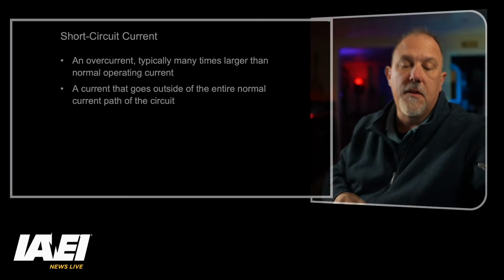So if you think about a circuit, and you have a circuit breaker back in your panel board, you have current coming out that hot wire, the black wire, like in a residential dwelling unit, from an NM wire perspective. It comes out that black wire and it comes back the white wire on a single phase 120 volt circuit. So I have a hot conductor and I have a grounded conductor, ungrounded conductor and a grounded conductor, and I have a load at the end. As long as current stays in the path, any current that exceeds the rating of the conductor or the equipment is an overcurrent, is an overload. Because remember, overcurrents are all encompassing. I have overloads, I have short circuits, I have ground fault currents. Those are all overcurrents.